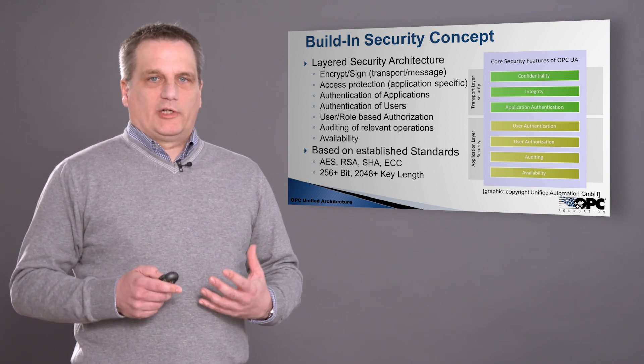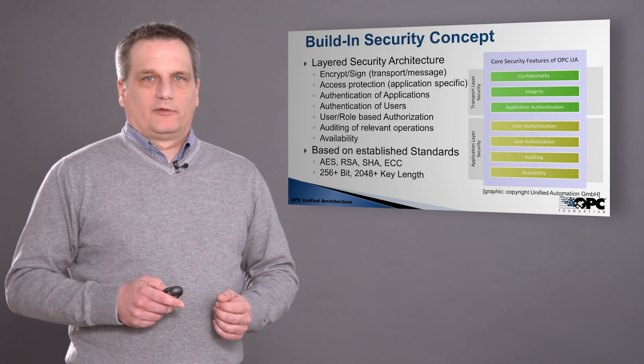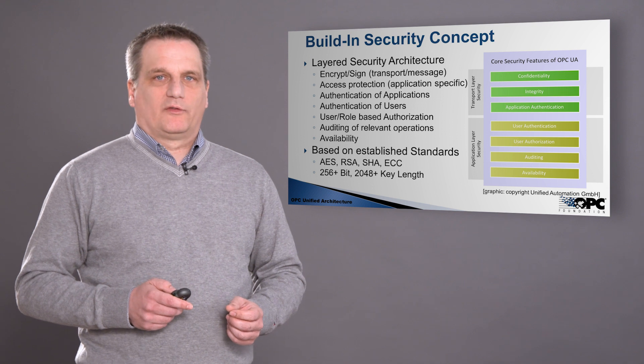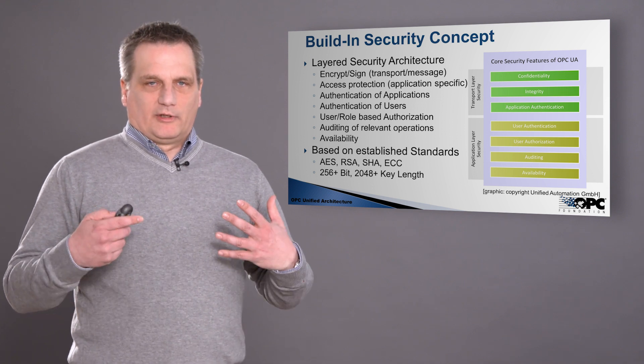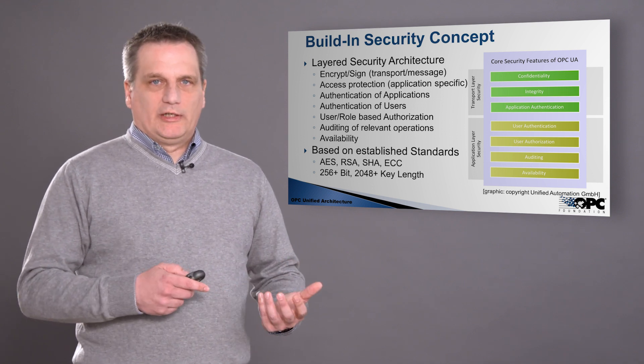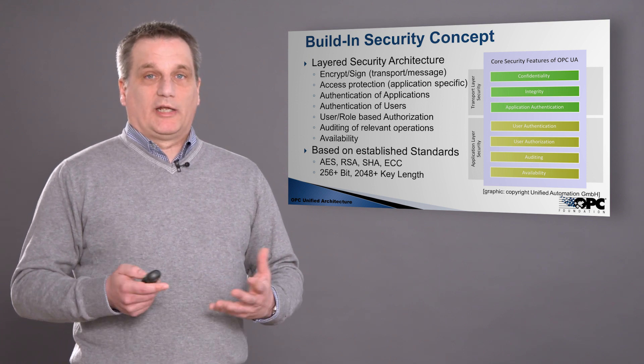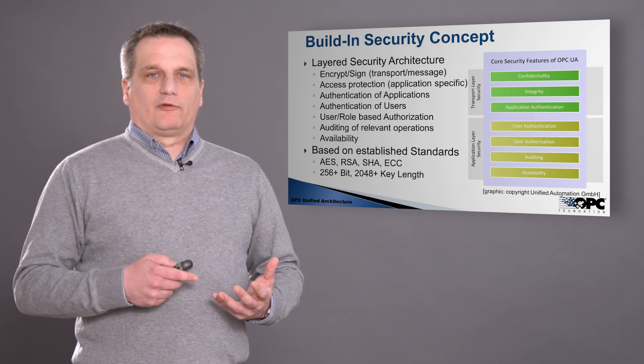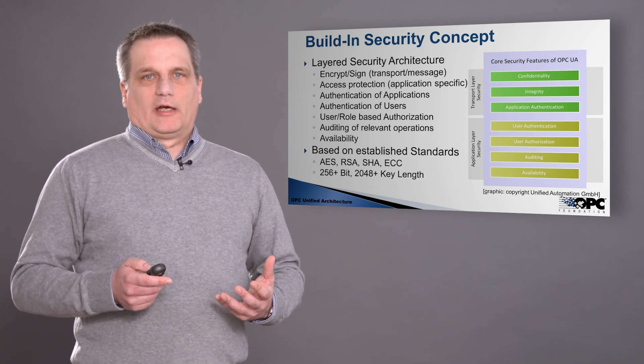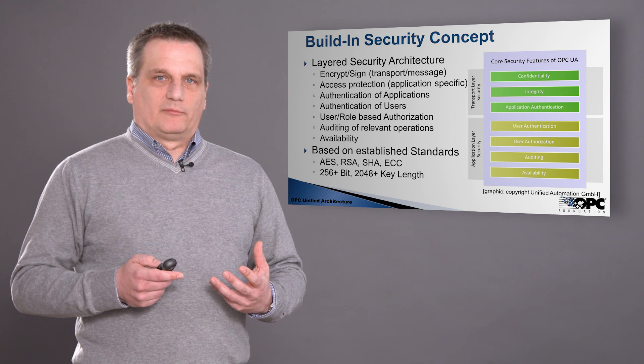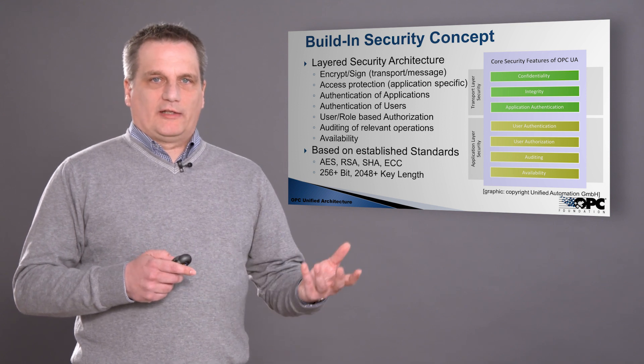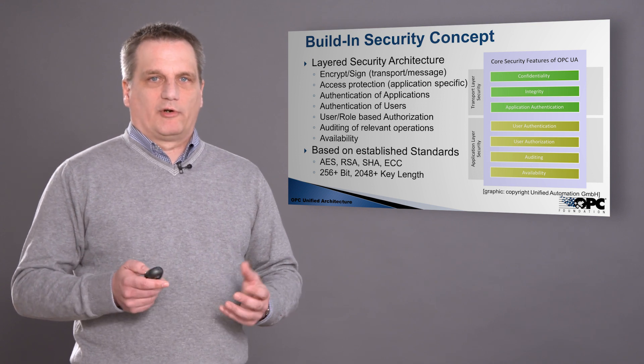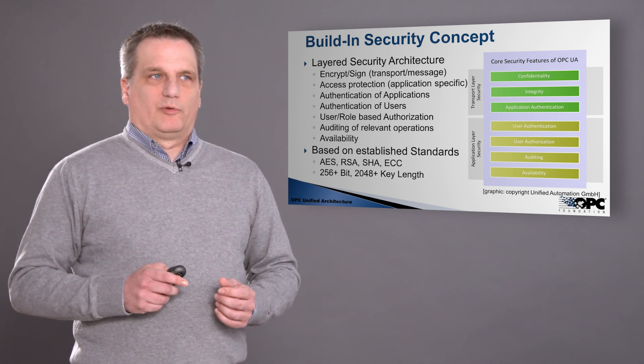We have access protection down to the node level. Every single node inside the OPC information space has an access right for read, for write, for being visible, for being executable. We can also authenticate users and identify them — for example, a guest is only allowed to read, an administrator is allowed to write, and this is an operator. So we have role-based permissions.